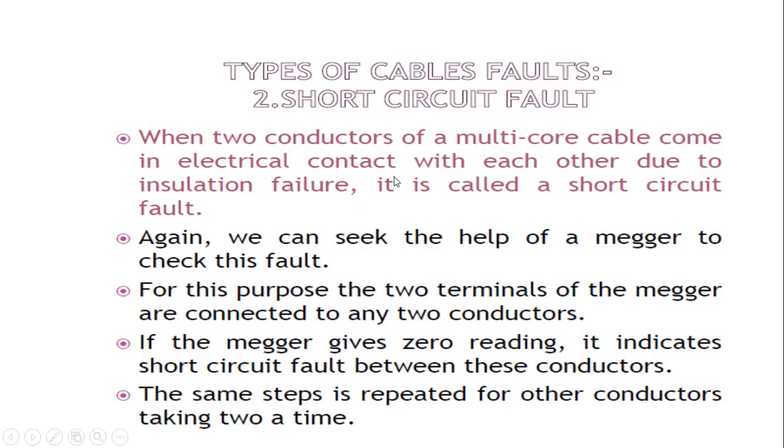If the insulation between the two conductors fails, then the two conductors come in electrical contact, and in that case short circuit faults are obtained. Therefore, again we can seek the help of a Megger to check this fault. By using the Megger, we identify the short circuit faults in the conductors.